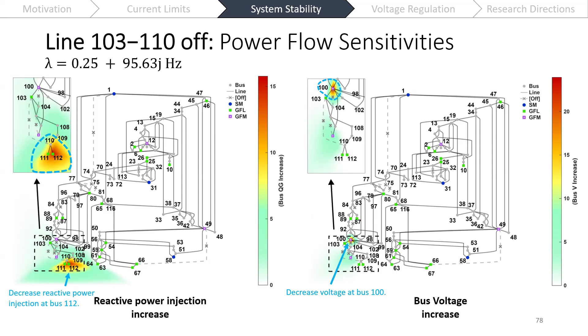So if we do the opposite of these actions, if we decrease the reactive power and we decrease the voltage, which we do here just a little bit after the line is switched off, we can see that our system actually becomes restabilized. We get adequate damping and we converge to a new steady state point. Switching the line back on a little bit later, our system then remains stable after that switch.